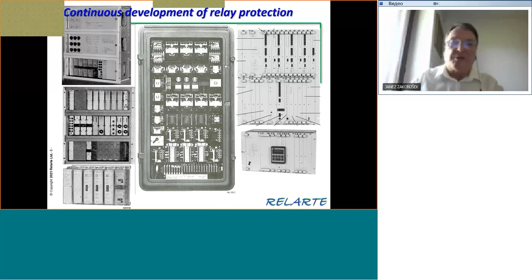And when they designed this relay, here it was called RELS 100, the capacity of the microprocessor was not really big enough to perform all necessary functionality. So to calculate impedance for phase-to-phase loops separately, for phase-to-earth loops separately, and for phase selection, they were using 3 additional digital signal processors. So that was also a very special approach during that period.